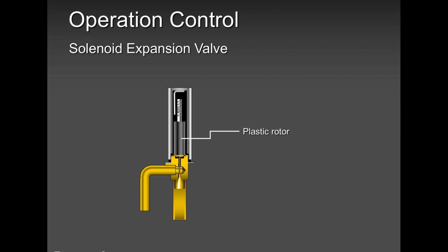The unit is going into pump down. Now you get mad at Tony. You get mad at me. You get mad with everyone. You told me to replace this, and I have the same problem. But you forgot to tell us that when you were replacing these, you didn't apply a cold cloth. Maybe you applied one, but it wasn't cold enough. So you're going to be super, super gentle, super, super careful, and use the correct size of torch nozzle. Apply the correct flame. Don't apply too much flame when you're replacing this electronic expansion valve.